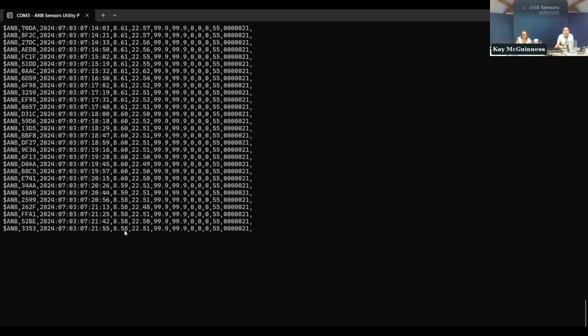We have the pH returned, and the temperature of the solution. Because this is outside of our current measurable salinity range, which is 0.3 to 7 ppt using the version 9 firmware, we output 99.9 where salinity and conductivity are placed. The next two zeros relate to the transducer and sensor health or diagnostics, and we'll show you why the sensor is smart with those outputs in a few minutes. The next zero is really a reserve byte; there's nothing in there. That's because we believe we're going to add extra functionality in the coming years, where we might output additional measurements from the sensor.